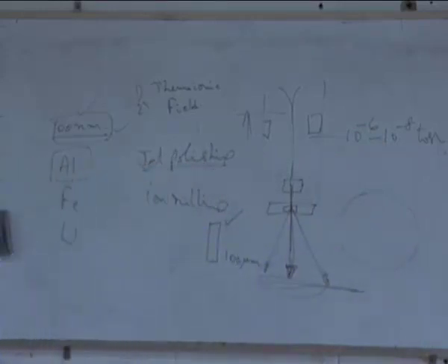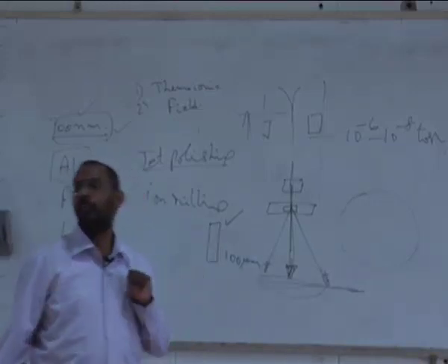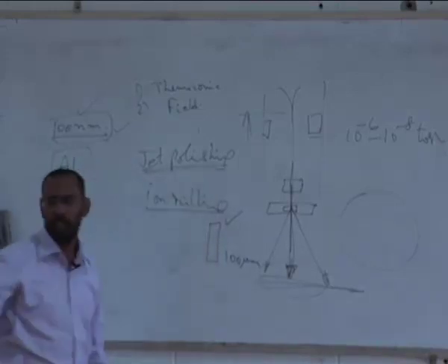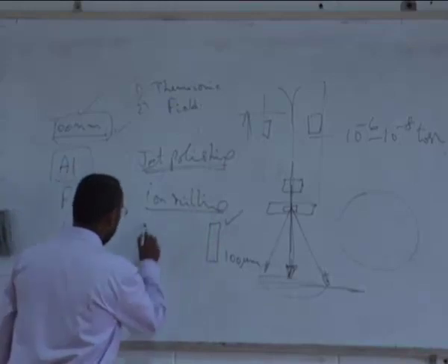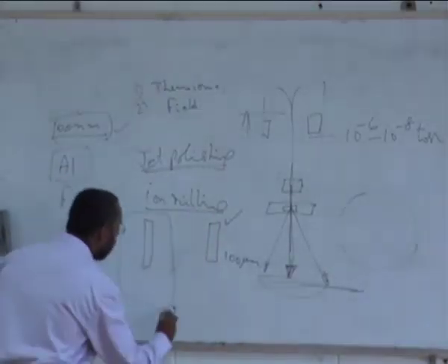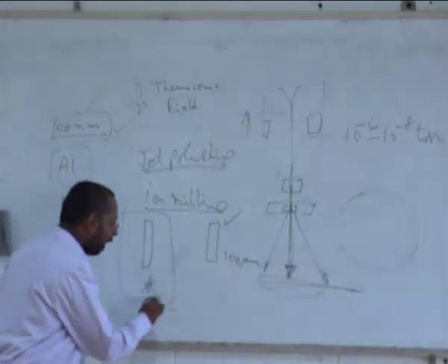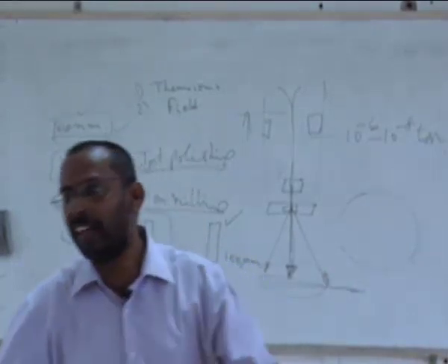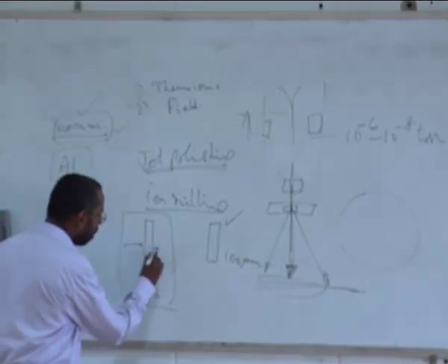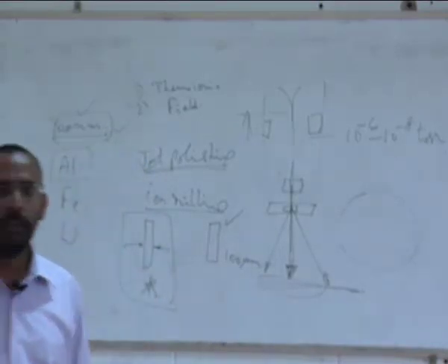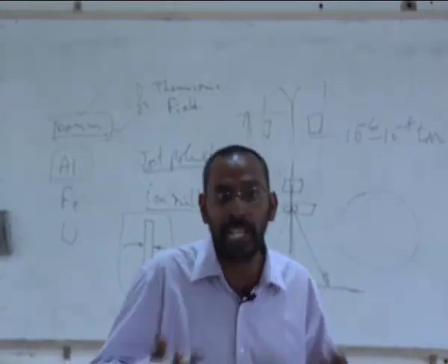So once you make a thin slice like this, similar to your metallic sample, that is when the whole story starts, and you do not use jet polishing, but you use what is called ion milling. What we do is we keep this thin sample in a chamber, evacuate it and fill it with argon, ionize this argon gas and allow these ions to fall on the sample like a beam from both directions. And we call this ion milling because you are milling.